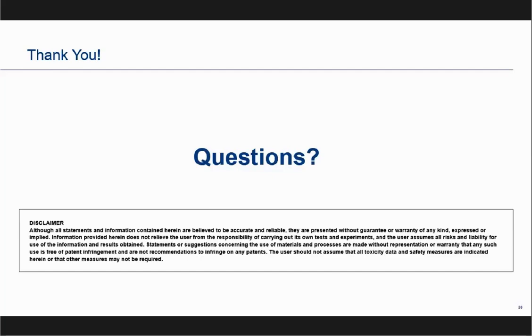We don't want you to select too large of a unit. For example, if you have a small walk-in cooler that would typically only need maybe a 1 horsepower condensing unit, we don't want you putting a 6 horsepower digital X-line on there. Now there is some wiggle room. We've had a couple folks say, I'm going to put 2 coolers on now, can I add a display case in the future, do I have enough extra capacity? And the way we sized that unit, yes, you can add that extra capacity in the future. So work with your application engineer to size it.